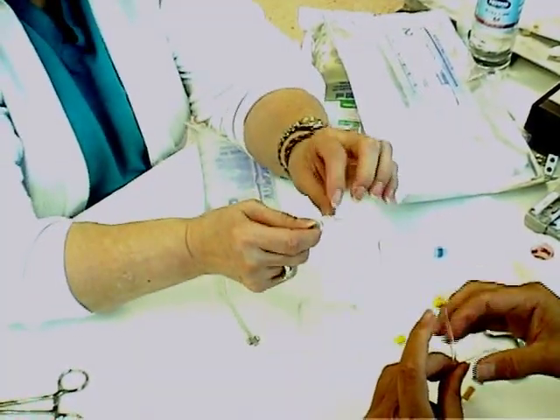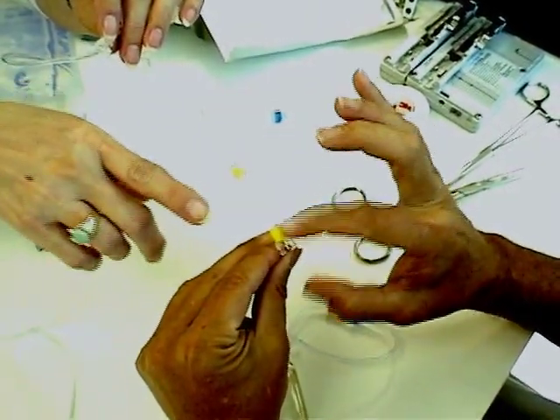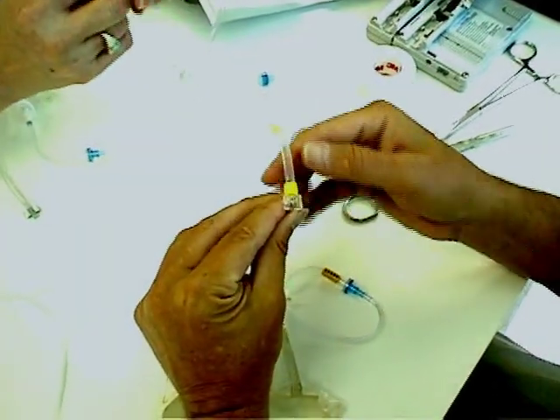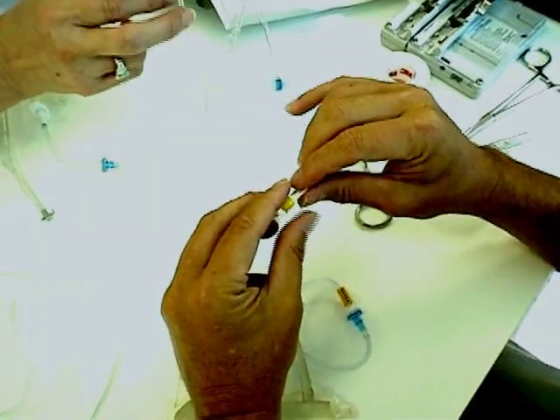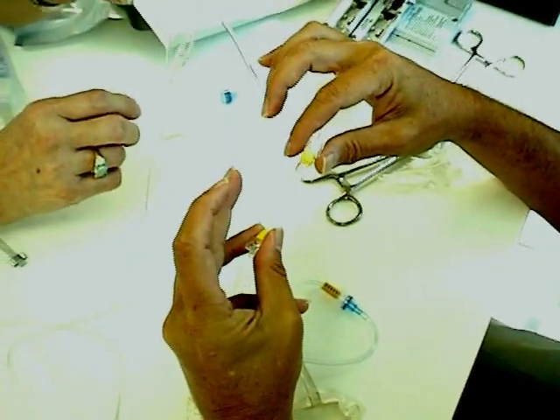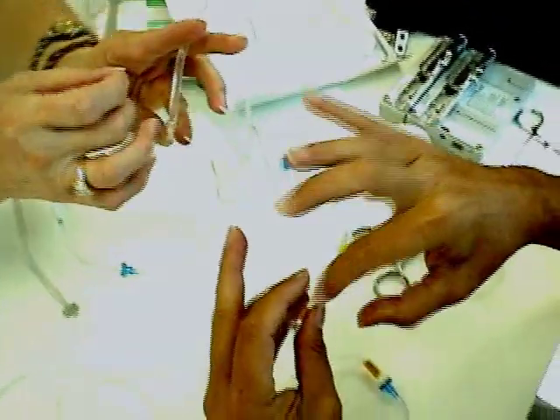Okay. Now when we get to this part right up here, see this little tab that's on there? That's the one that connects in with the sensor and the pump, and it tells the pump that there's a set in there. So we want to be very careful with that and not break it off, because if it breaks off, then the tubing is useless for us. So put your thumb over that, thumb and pinky, and then stretch. That way the thumb protects your little tab there. Okay.